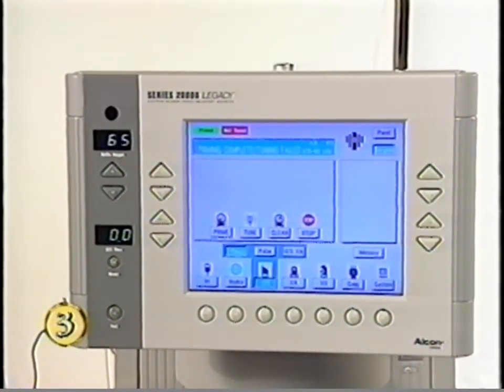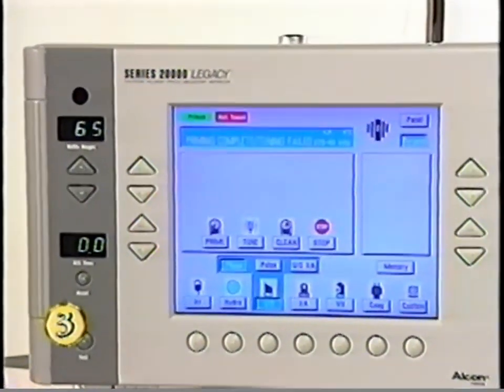In the alternate procedure, do not start test priming until the test chamber is filled. Begin the prime sequence for priming, vacuum and vent testing, and tuning. Press the test button twice in the US phaco mode to begin priming. Note that in the alternate method, there is no automatic reprime.